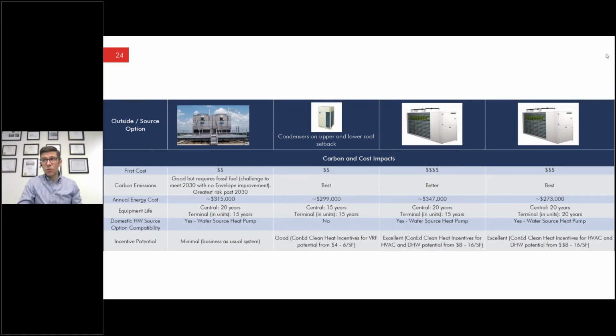Increasingly, in an existing building scenario where we're converting an old building to an all-electric solution, we look at a phased approach, often using a water source heat pump as the solution, and over time phasing in what that heat addition source is. Some of those buildings have Con Ed steam. We're starting with, in the short term, Con Ed steam can still be the heat addition to the condenser water loop, and over time phasing that into an all-electric solution, depending on how that works with carbon and Con Ed steam over the long term. Does that answer the question? We do look at it, but this particular study was focused specifically on trying to be all electric within the building. That was one of the reasons.